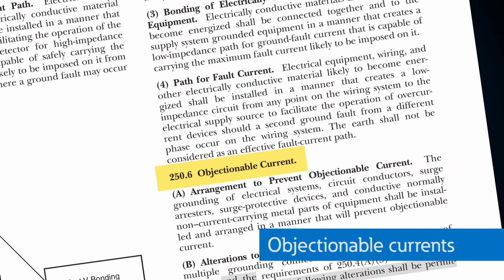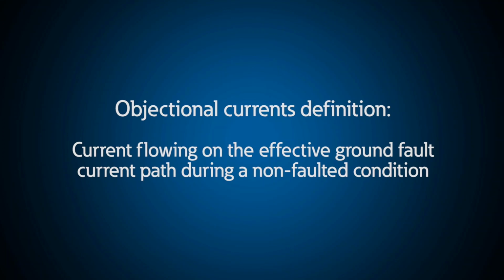All right, last statement about grounding: objectionable currents. We use this term objectionable currents in Article 250 of the National Electrical Code, but there's no definition in the NEC. And when there's no definition, you know what you do? You make it up. So this is my definition: current flowing on the effective ground fault current path during a non-faulted condition.